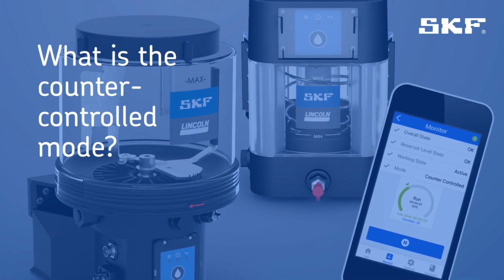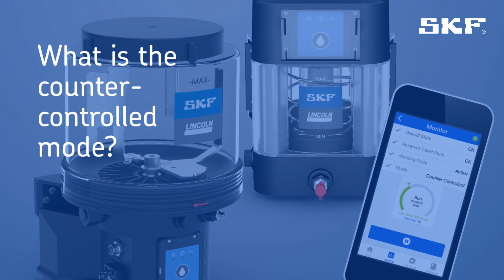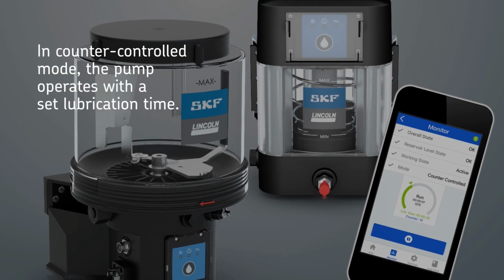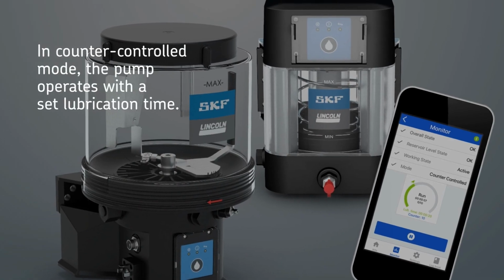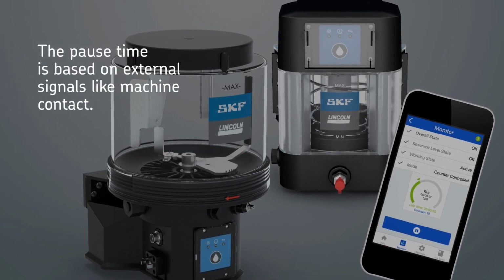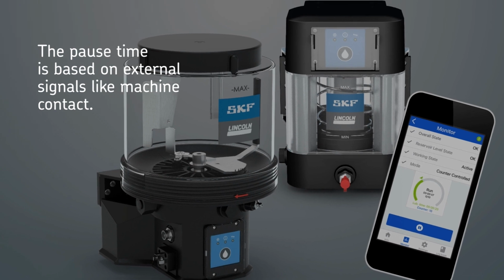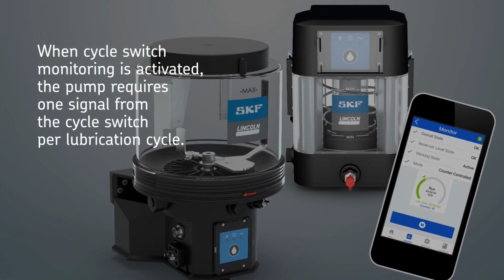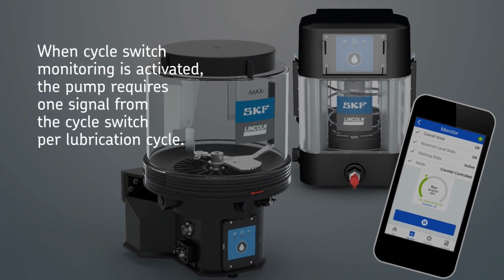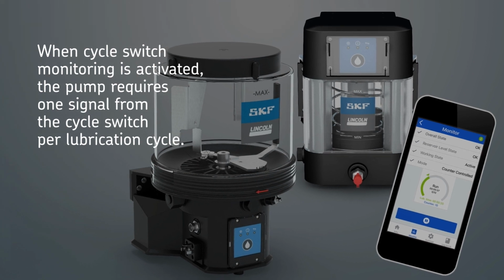What is the counter-controlled mode? In counter-controlled mode, the pump operates with a set lubrication time. The pause time is based on external signals like machine contact. When cycle switch monitoring is activated, the pump requires one signal from the cycle switch per lubrication cycle.